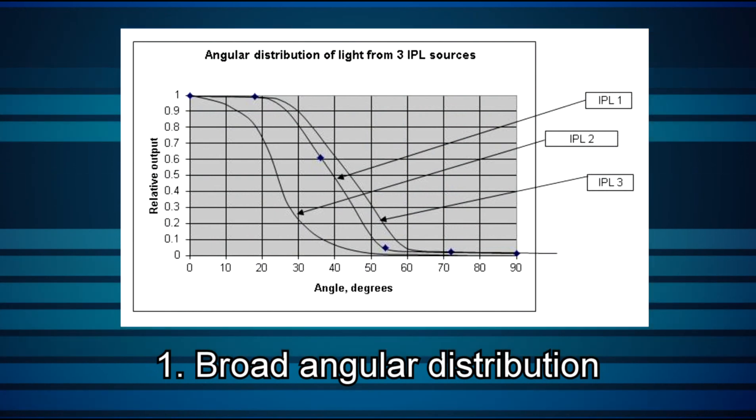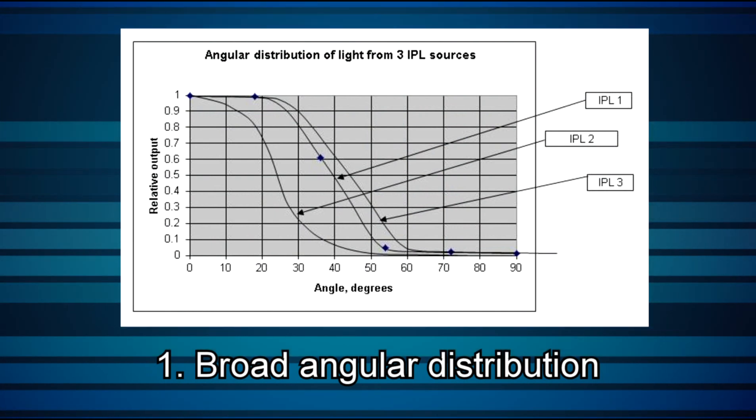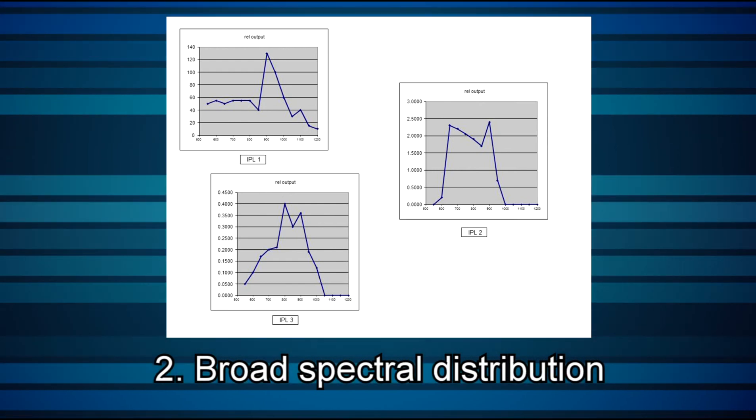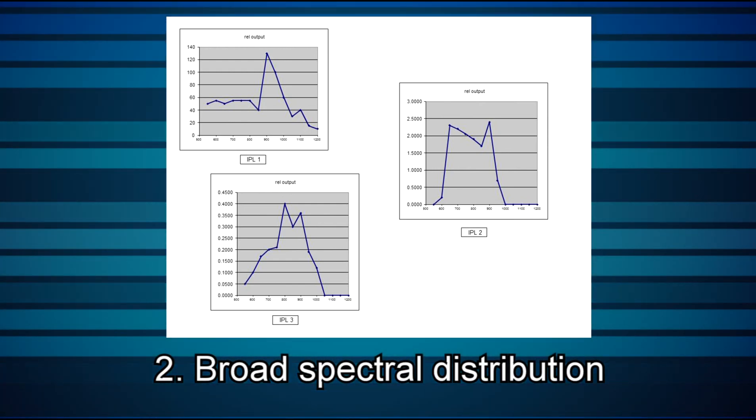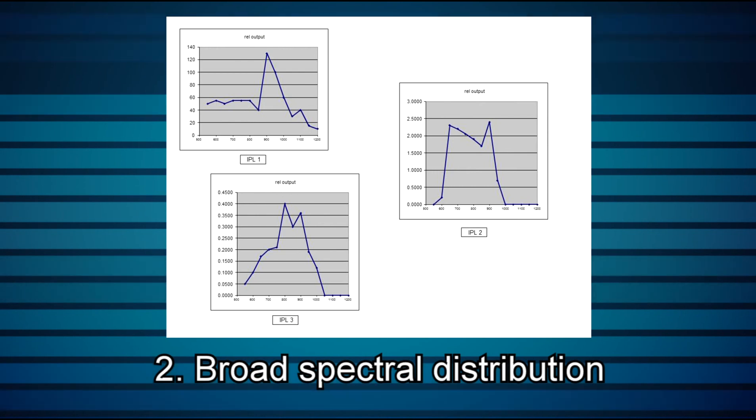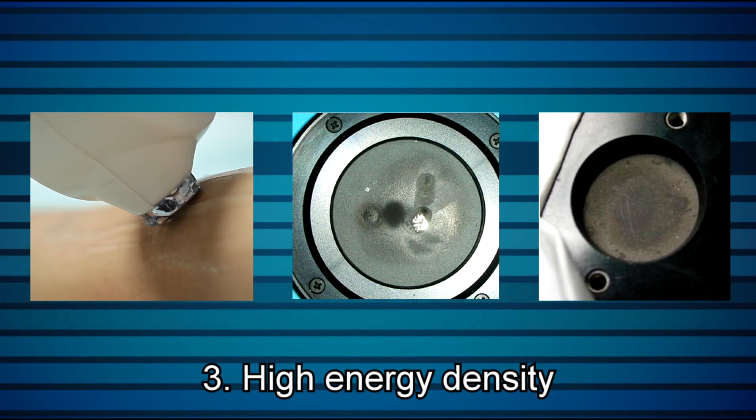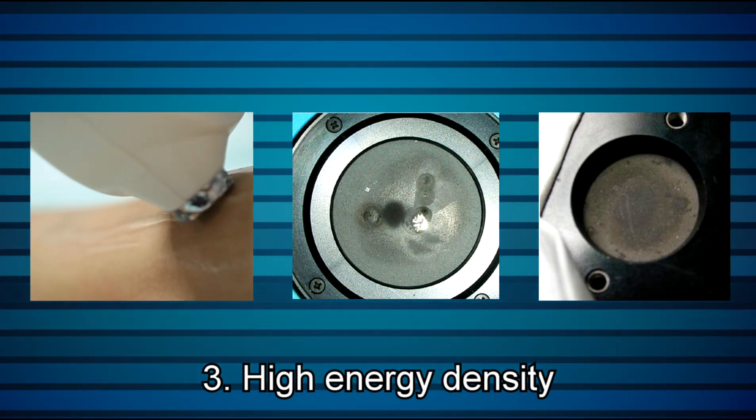Measuring the energy of an IPL pulse, though, is tricky. IPL sources present some unique challenges when it comes to measuring them: 1. Broad angular distribution, which makes it difficult to capture the full beam. 2. Broad spectral distribution, which makes it difficult to maintain accurate calibration. 3. High energy and energy density, so the sensor's absorber had better be able to take it without damage.